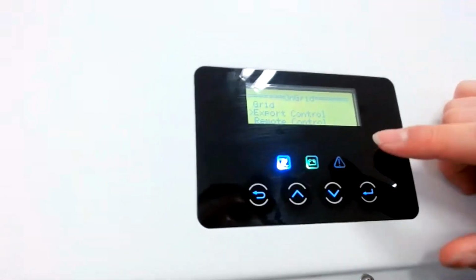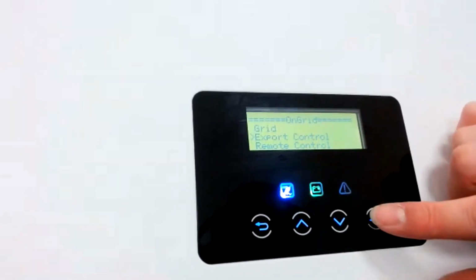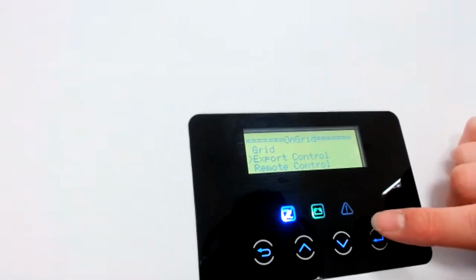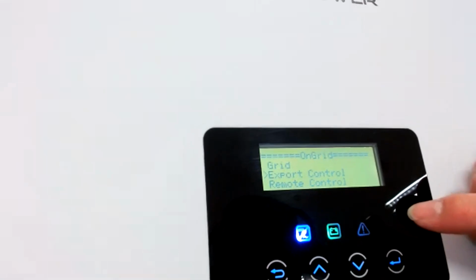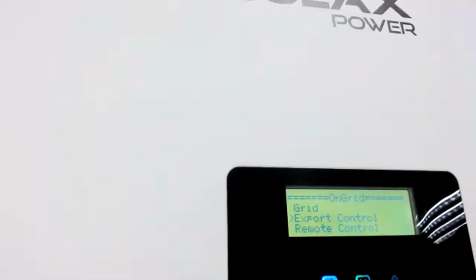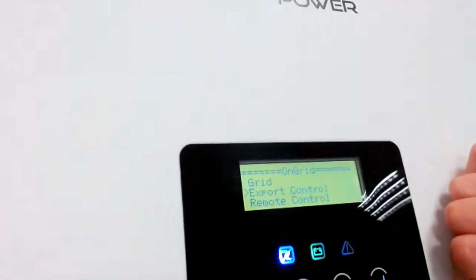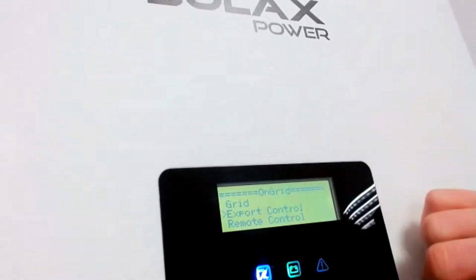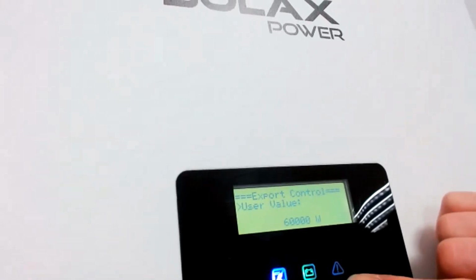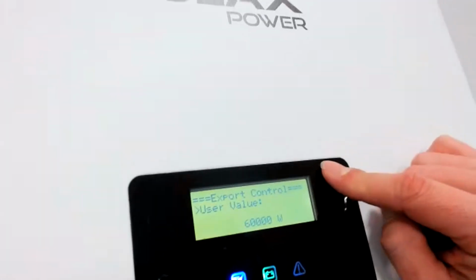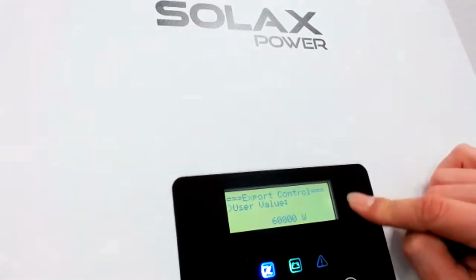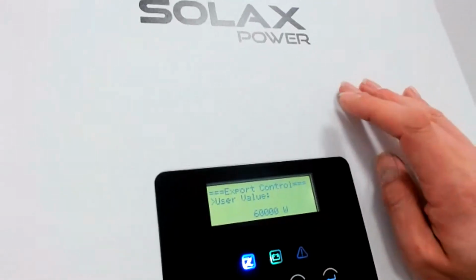The next point is export control, this is our dynamic power limitation. With this option, you always need a meter, either the SDM230 or the SDM630, depending on how many phases your system has. In this export control, you type in 70%, for example, of the power on the roof. For example, you have 10 kilowatt peaks on the roof, so you type in 7,000 watts, and the energy output to the grid will be limited to 7,000 watts.